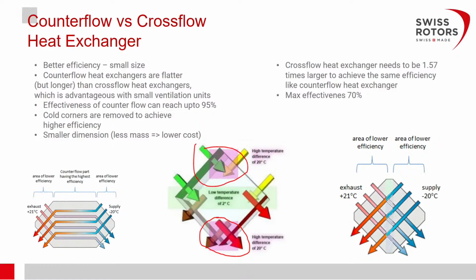So once again, the differences and the advantages. We have better efficiency. The counterflow heat exchangers are flatter, of course, a bit longer than the crossflow. And this is an advantage for some suspended small units. Effectiveness of the counterflow can reach 95%. And the cold corners are removed, so especially here in the cold climate in Europe, there will not be such a possibility of freezing inside the heat exchanger.